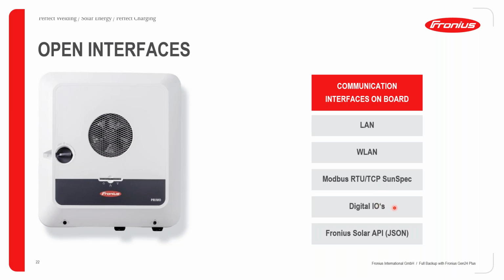Your digital input-output ports are very handy when you want to send a signal to a relay, okay? And that relay can then be triggered to open or close, which can then trigger a load to either switch on or switch off, which, as I said earlier on, could be very handy if you want to switch on heat pumps or switch off heat pumps, or even if you want to switch on your air conditioning system when a certain power threshold is reached in the day.